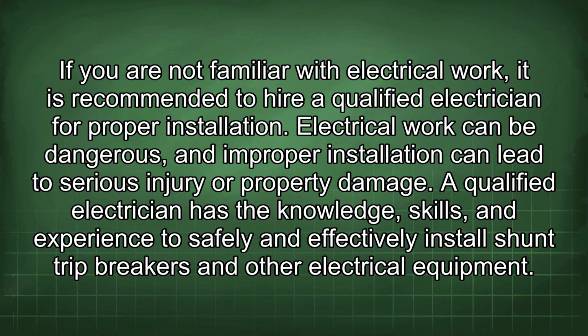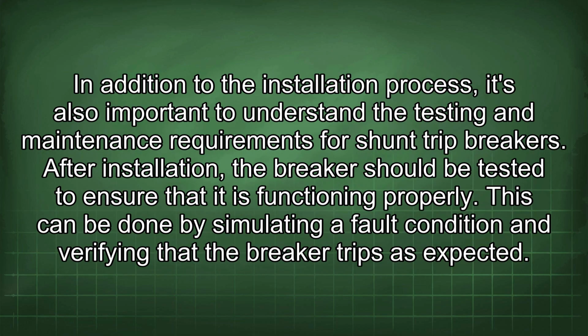A qualified electrician has the knowledge, skills, and experience to safely and effectively install shunt trip breakers and other electrical equipment. In addition to the installation process, it's also important to understand the testing and maintenance requirements for shunt trip breakers. After installation, the breaker should be tested to ensure that it is functioning properly. This can be done by simulating a fault condition and verifying that the breaker trips as expected.